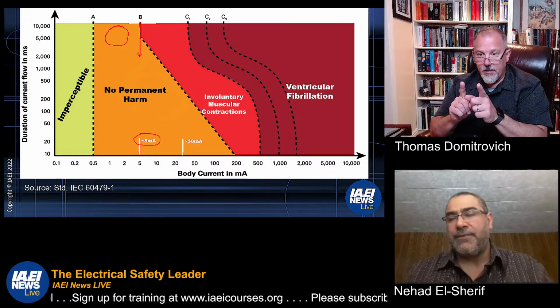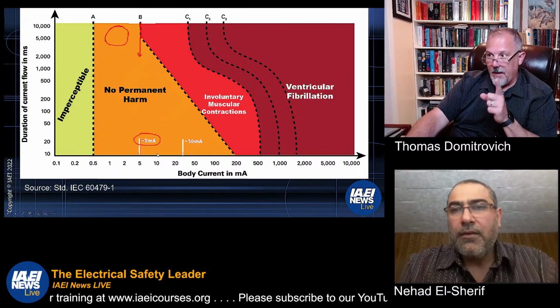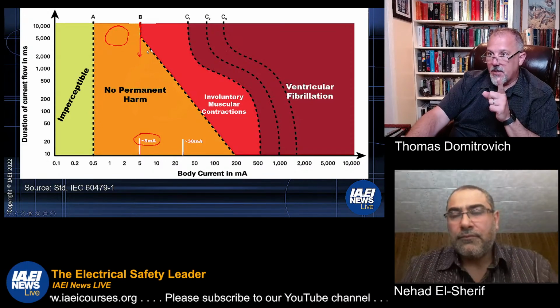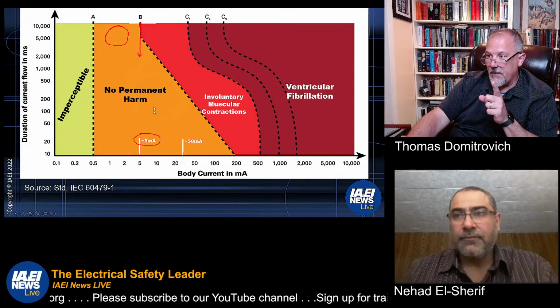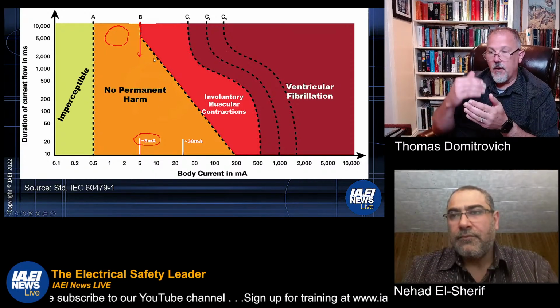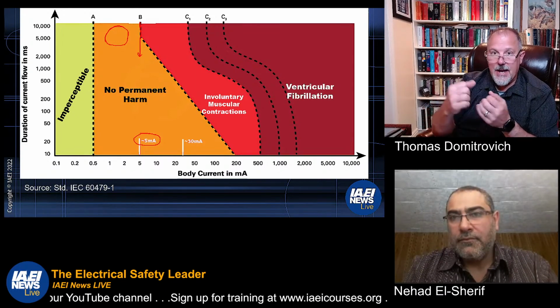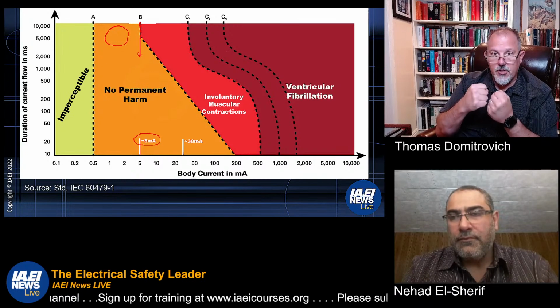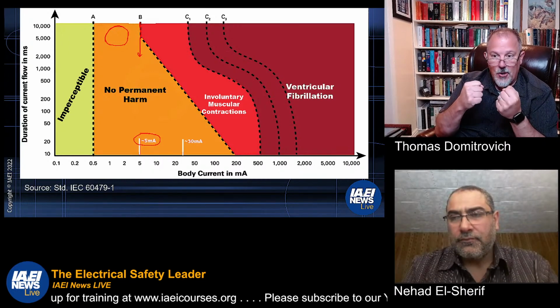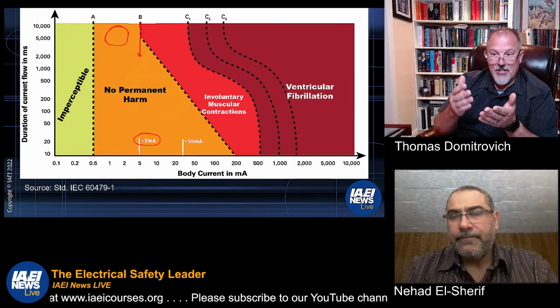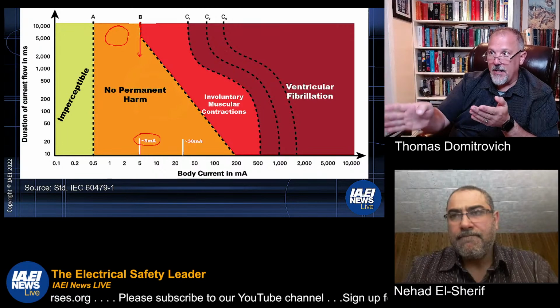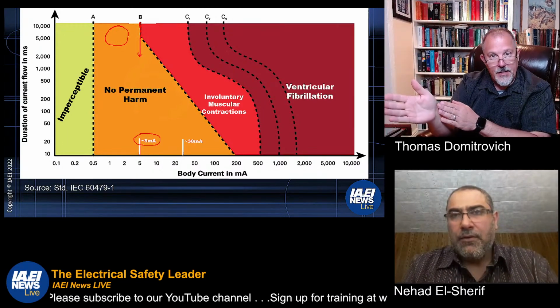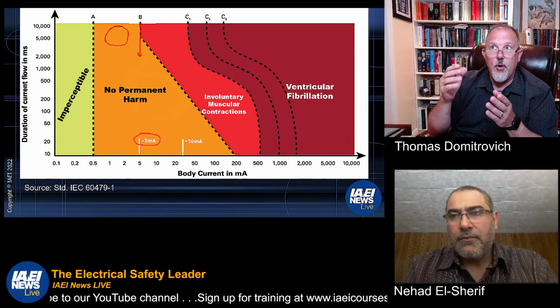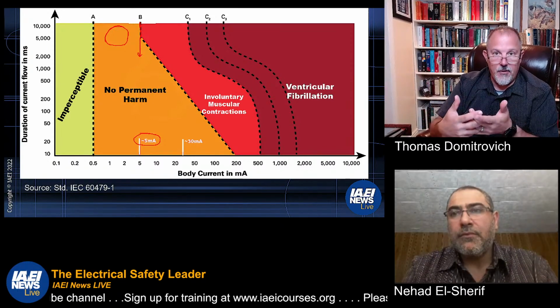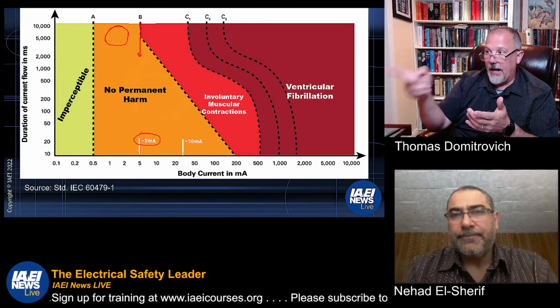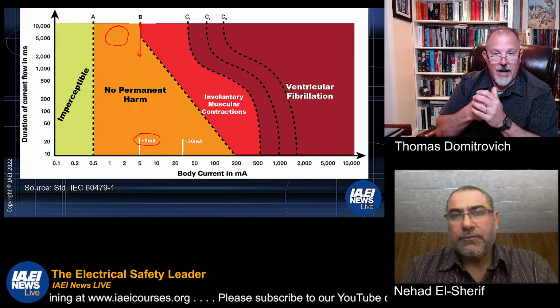So in other words, at around 10 milliamps, you have 2,000 milliseconds. So that 10 milliamps can flow through your body for up to 2,000 milliseconds. After the 2,000 milliseconds, now you're getting to a point where you have involuntary muscle contractions. But nobody has the full control of being able to let go that fast, right? So that's why that 5 milliamp line is where we operate. Anything above that, we want to make sure that we remove the current passing through your body fast, so that you don't end up in that involuntary muscle contraction situation.